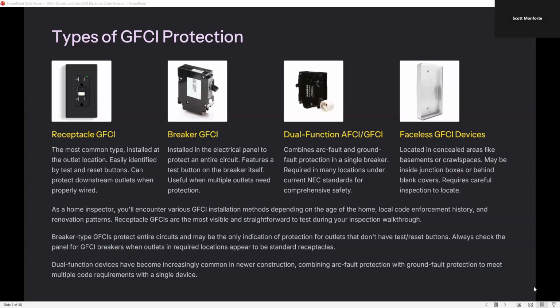Types of GFCI protection. So we have the GFCI receptacle, the most common type, installed at the outlet location. Easily identified by test and reset buttons, it can protect downstream outlets when wired properly. We have a GFCI breaker installed in the electrical panel to protect the entire circuit. It features a test button on the breaker itself, useful when multiple outlets need protection. Dual function AFCI/GFCI combines arc fault and ground fault protection in a single breaker, required in many locations under the NEC standards for comprehensive safety. Then we have our faceless GFCI devices, located in concealed areas like basements or crawl spaces, maybe inside junction boxes or behind blank covers. They require careful inspection to locate.